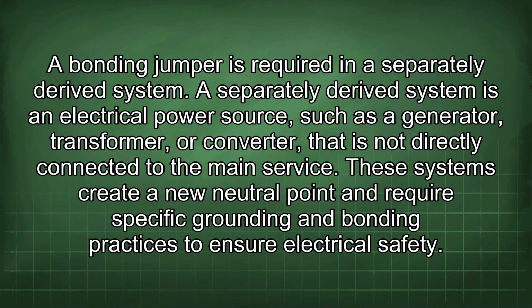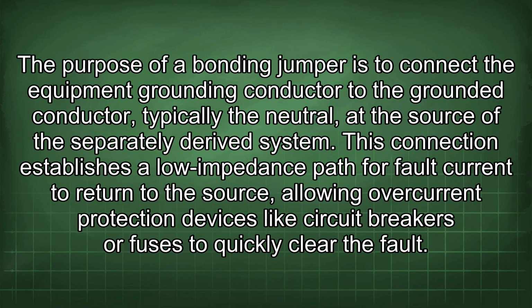A bonding jumper is required in a separately derived system. A separately derived system is an electrical power source, such as a generator, transformer, or converter, that is not directly connected to the main service. These systems create a new neutral point and require specific grounding and bonding practices to ensure electrical safety. The purpose of a bonding jumper is to connect the equipment grounding conductor to the grounded conductor, typically the neutral, at the source of the separately derived system.